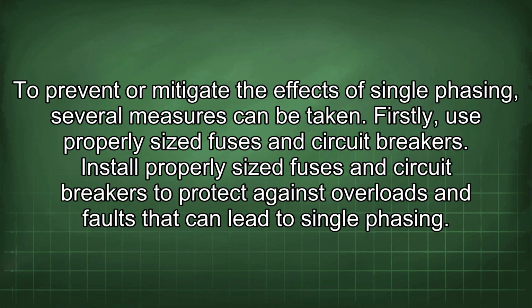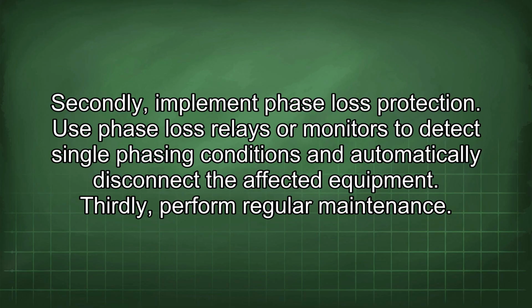To prevent or mitigate the effects of single phasing, several measures can be taken. Firstly, use properly sized fuses and circuit breakers. Install properly sized fuses and circuit breakers to protect against overloads and faults that can lead to single phasing. Secondly, implement phase loss protection. Use phase loss relays or monitors to detect single phasing conditions and automatically disconnect the affected equipment.